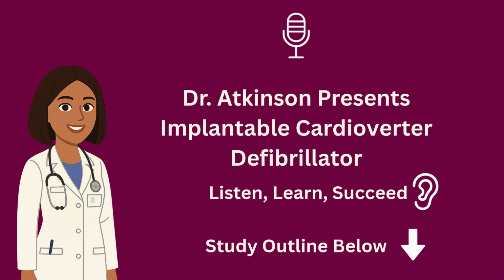A newer alternative is the subcutaneous ICD, or S-ICD, which avoids vascular access and is most appropriate for patients who do not require pacing or cardiac resynchronization therapy. As with pacemakers, ICDs have a coding system. The first letter identifies which chamber is shocked, the second indicates the chamber that can be antitachycardia paced, the third shows whether the device uses electrograms or hemodynamics to detect tachycardia, and the final letter indicates the chamber that has anti-bradycardia pacing.